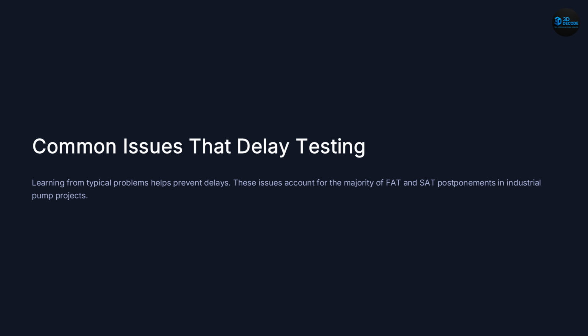Next, common issues that delay testing. Let's talk about reality, because almost every project experiences delays, and the causes are remarkably similar: incomplete calibration, alignment issues, seal system problems, unresolved punch list items, piping strain, control system issues. Most delays aren't complicated engineering problems. They're closure problems. Work that should have been completed earlier, which is why structured checklists are so powerful. They expose missing items before they become schedule problems, and preventing delays is always cheaper than recovering from them.